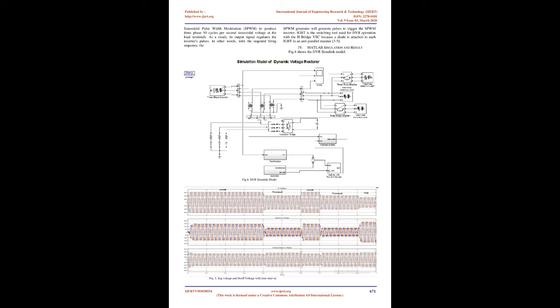A simple output filter is required at the converter output to get a smooth and sinusoidal output voltage. The input to the filter is a 50 Hz AC signal modulated with high frequency. For the suggested case, the switching signal that modulates the 50 Hz signal is taken as 5.5 kHz. A low-pass LC filter is therefore suggested that suppresses most of the harmonic frequencies produced. This will result in an output voltage that is almost sinusoidal.